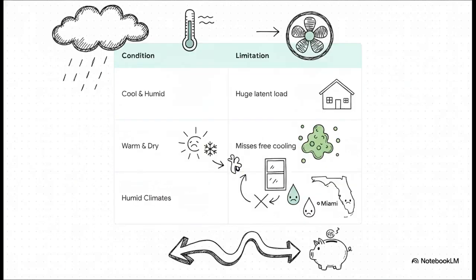But here's the catch, and it's a big one: humidity. A fixed dry bulb literally cannot feel moisture, so it might see 68 degrees outside and happily open the vents, completely blind to the fact that it's sitting at 80% relative humidity. It just pulled cool, damp air into your building, forcing your system to work overtime to dehumidify that massive latent energy load. In humid climates, like down in Zone 1A in Miami, this could lead to unacceptable indoor humidity and, worst case, severe mold risks. On the flip side, on a warm but super dry day at 73 degrees and 30% humidity, it might just shut off prematurely, completely missing out on great cooling opportunities. Oh, and add in a standard sensor accuracy of plus or minus 2 degrees. Yeah, your energy bills can definitely take a hit.